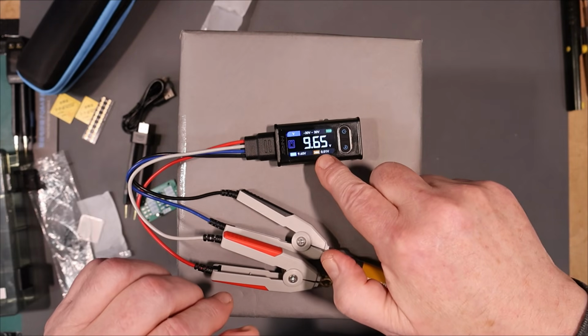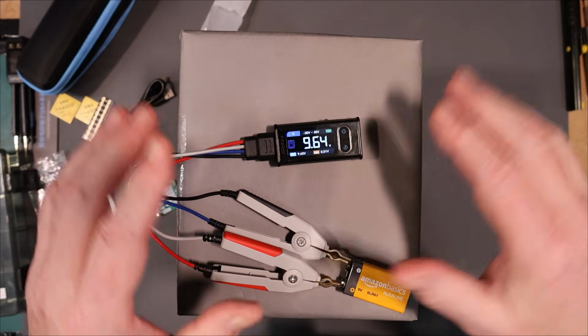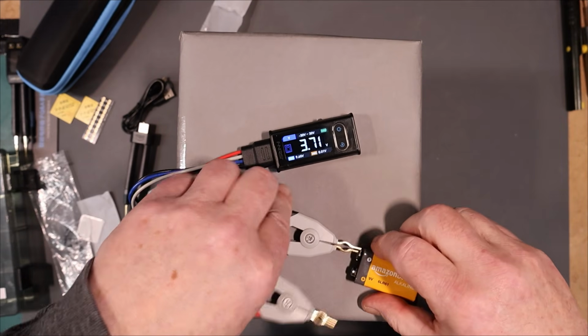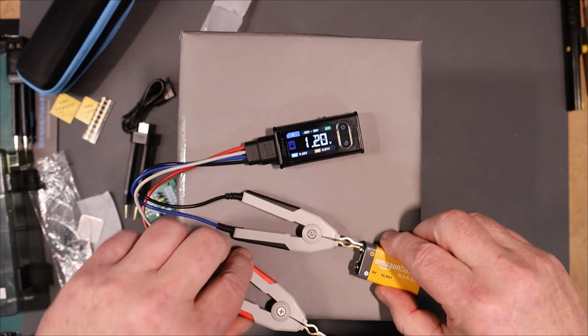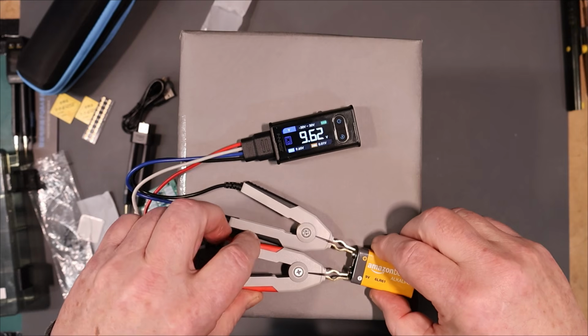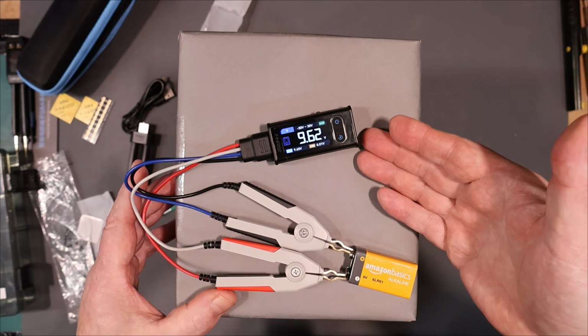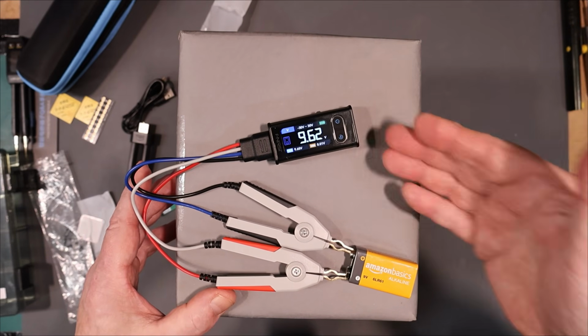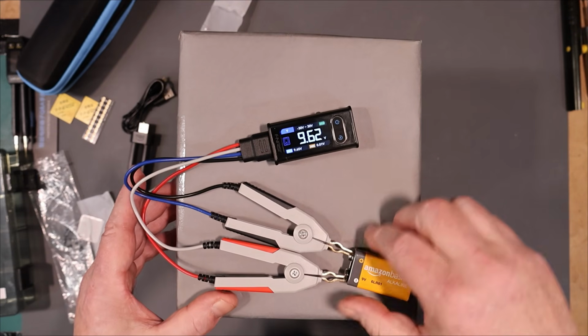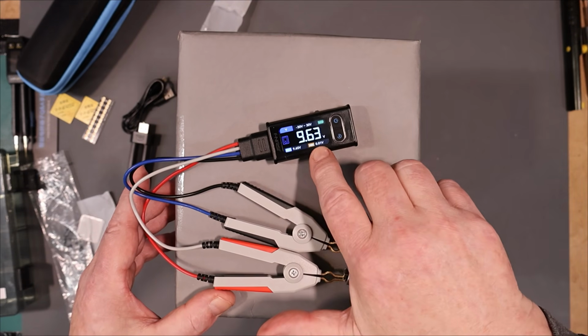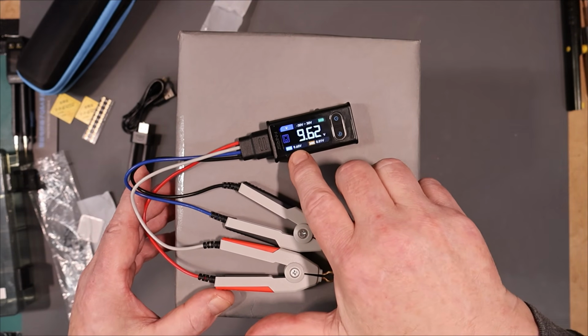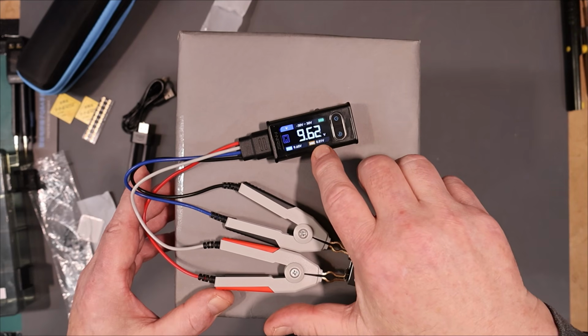Now, what does it say? 9.65 here, 9.64, 9.65. And what's it say the other way around? If there's a significant difference, that's a bit of a problem. No, the difference is less than 0.02 volts, so that's really good. And it keeps track of the maximum and minimum there - 9.65 was our maximum voltage, and our minimum voltage it read was 0.01 volts. Good.